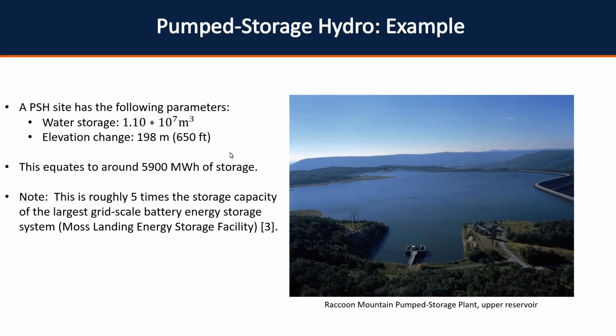This is pretty close to what we actually have at one of our generation sites. We have about 1.1 times 10 to the 7th cubic meters available to generate at an elevation of 198 meters. That's about 5,900 megawatt hours of storage. I think it's pretty average for a pump storage site, but to put it in some kind of comparison, that's about 5 times the storage capacity of the largest grid scale battery energy storage system. That might be a little outdated, but I think it's still relevant.